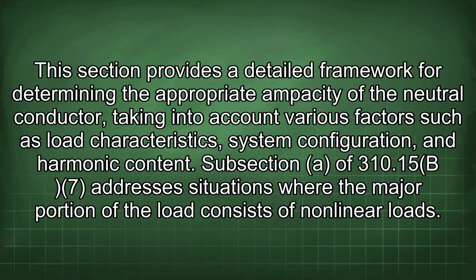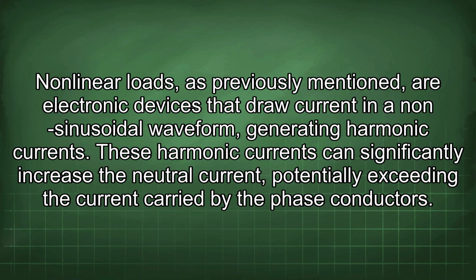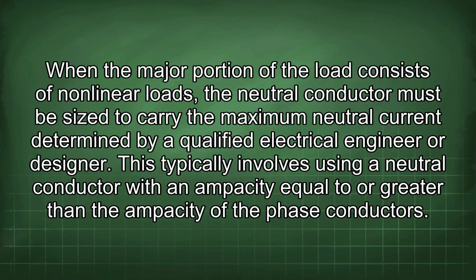Subsection A of 310.15(B)(7) addresses situations where the major portion of the load consists of nonlinear loads. Nonlinear loads, as previously mentioned, are electronic devices that draw current in a non-sinusoidal waveform, generating harmonic currents. These harmonic currents can significantly increase the neutral current, potentially exceeding the current carried by the phase conductors. When the major portion of the load consists of nonlinear loads, the neutral conductor must be sized to carry the maximum neutral current determined by a qualified electrical engineer or designer. This typically involves using a neutral conductor with an ampacity equal to or greater than the ampacity of the phase conductors.